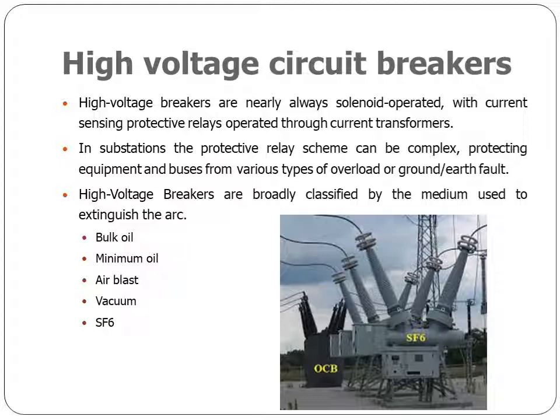The last one, high voltage circuit breakers. High voltage breakers are nearly always solenoid operated, with current sensing protective relays operated through current transformers. In a substation, the protective relay scheme can be complex, protecting equipment and buses from various types of overloads or ground and earth faults. High voltage breakers are broadly classified by the medium used to extinguish the arc: bulk oil, minimum oil, air blast, vacuum, and SF6. Okay, this is an example diagram illustrating an SF6 circuit breaker. Normally this type of circuit breaker is used in the substation.